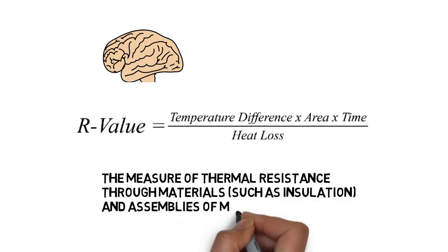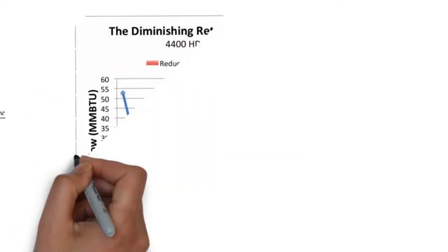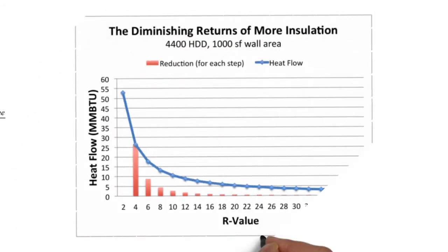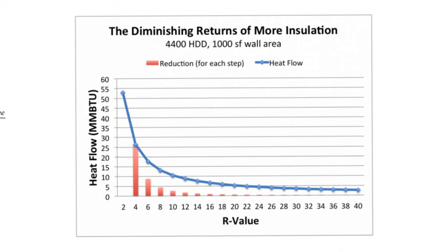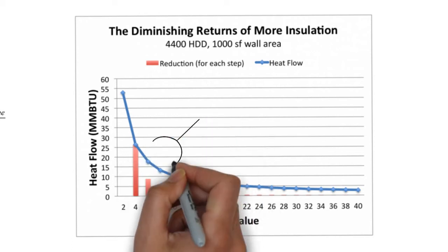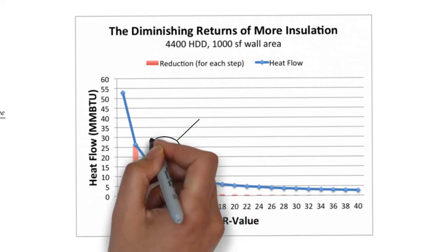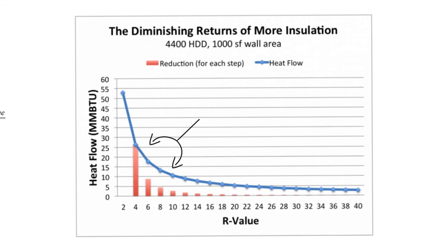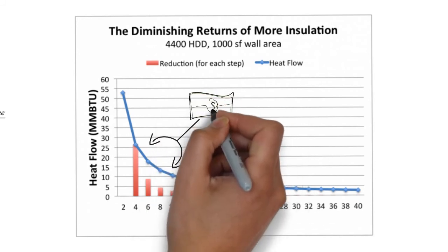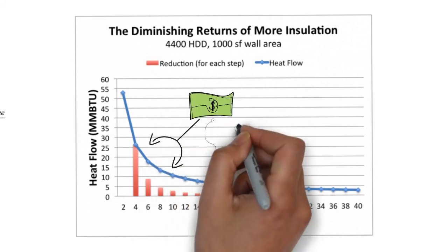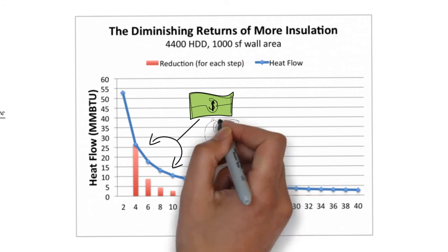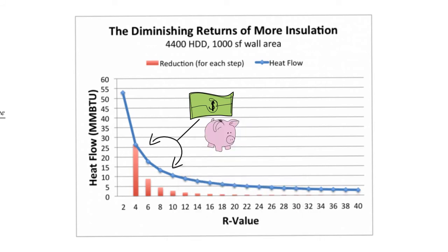In this graph we can see that adding any insulation to an uninsulated home can save much more energy than adding more insulation to an already insulated home. The most energy savings occur initially when you gradually increase your R-value. Optimal values are between 4 and 8. Adding much more insulation beyond that won't bring significant savings, and the cost will be much higher.